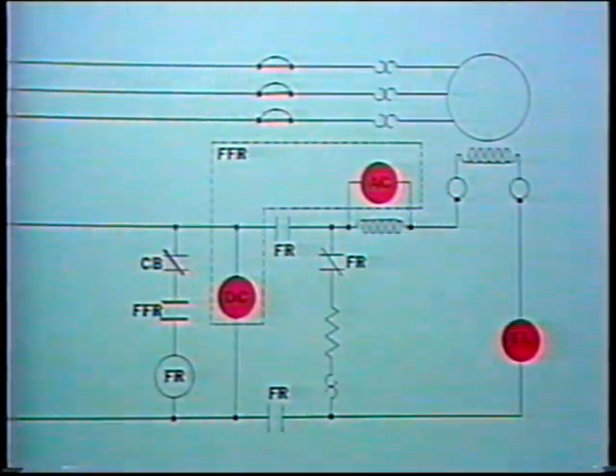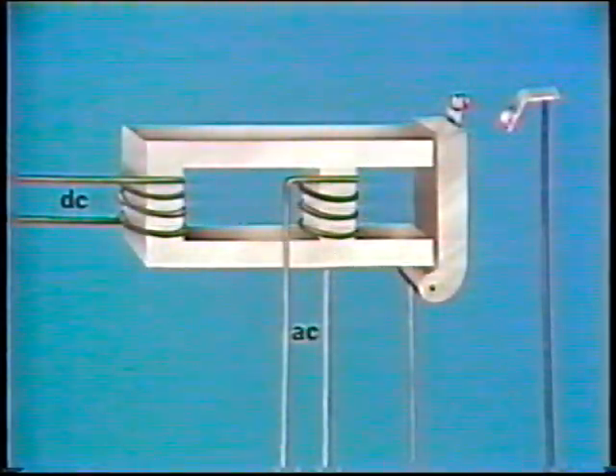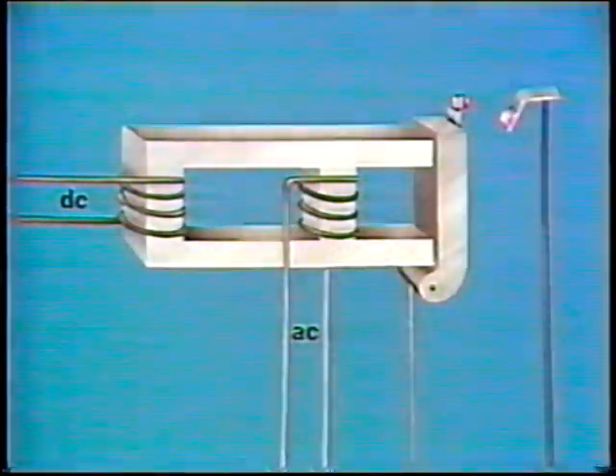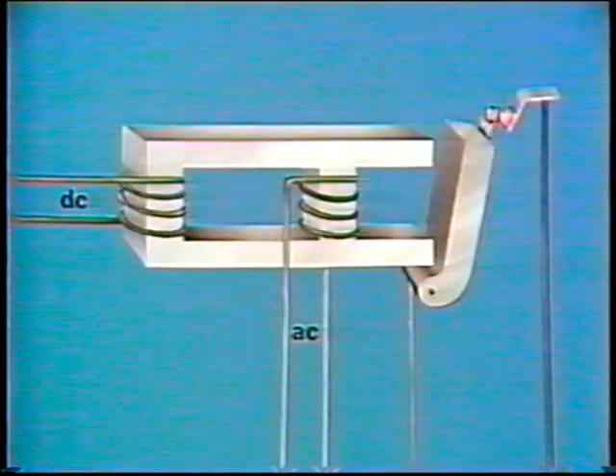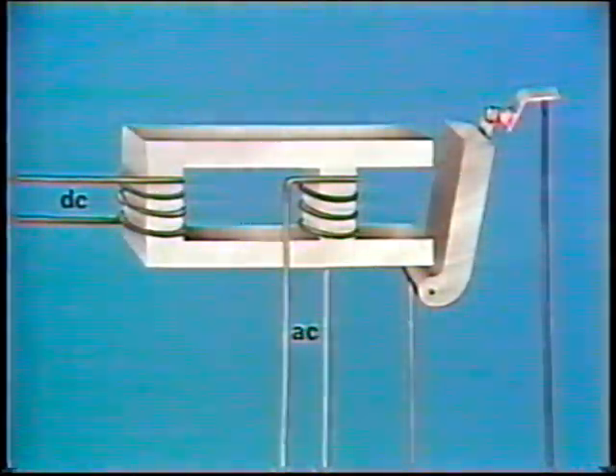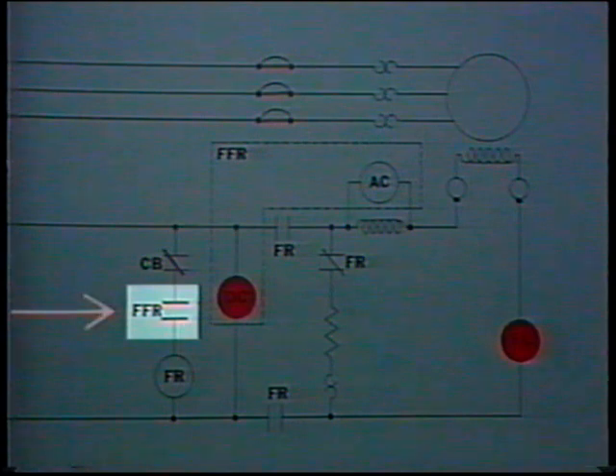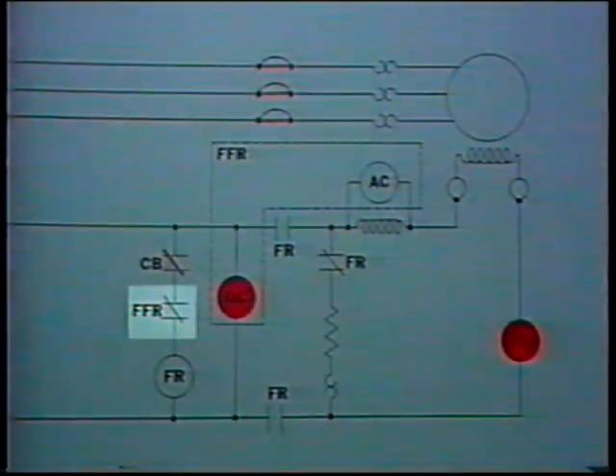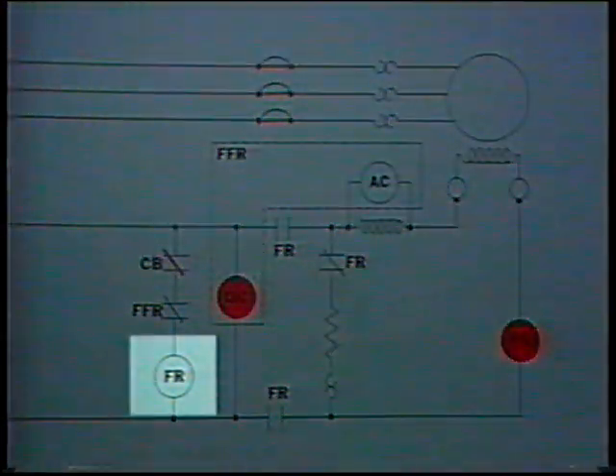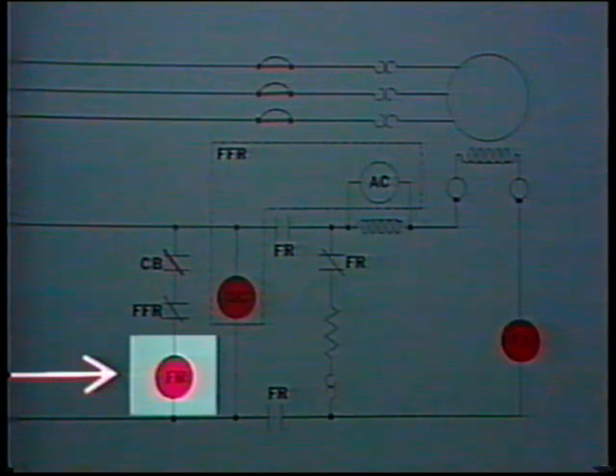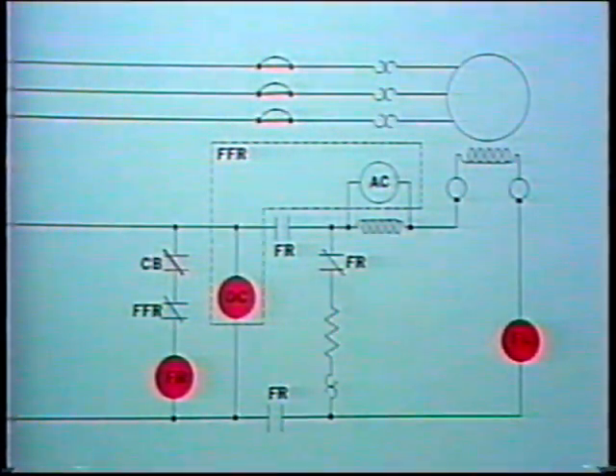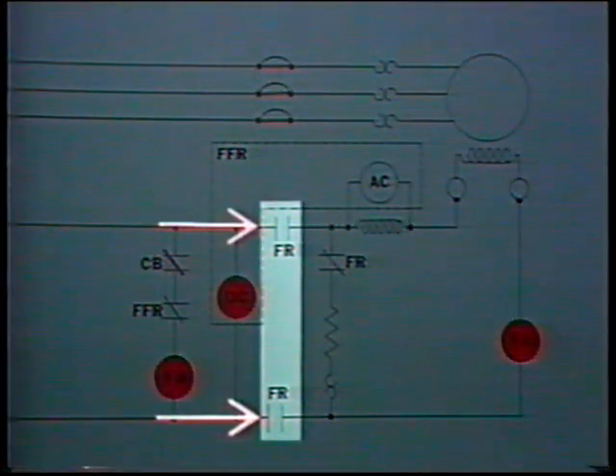The electromagnetic field of the AC coil, therefore, becomes weaker as the rotor approaches synchronous speed, and it is unable to aid the DC coil in holding the relay's contacts open. The contacts drop into a closed position. When the field frequency relay contacts close, the circuit from the DC power supply through the operating coil of another relay is complete. This relay is called a field relay, and its main function is to close the circuit from the DC power supply through the rotor.